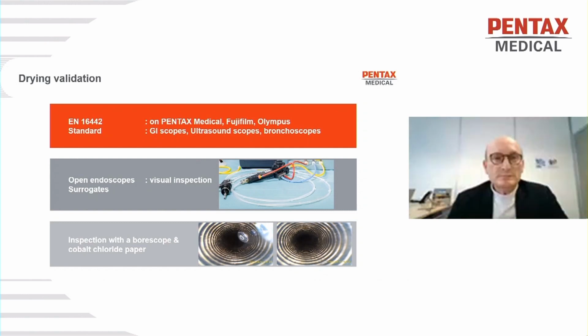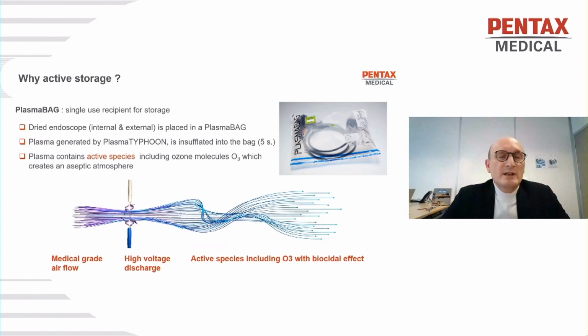So why active storage? The process for the storage is the following. Firstly, we dry the channels with the Plasma Typhoon. The external part is dried by the operator using an air gun or a lint-free cloth. After this, we place the scope in the plasma bag, and the Plasma Typhoon generates a plasma which is insufflated into the bag during a very short cycle, 5 seconds. The plasma contains active species, including ozone molecules, which create an aseptic atmosphere inside the bag.